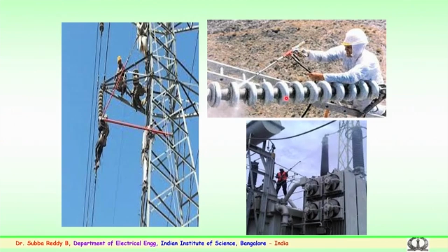de-energized method. This is a different method, particularly a handheld water jet of known spray targeted at the insulator surface. Both on the surface and on the petticoats, the cleaning is done to the insulators in de-energized conditions. As mentioned, the water resistivity and the solvents being used also play a role in cleaning aspects.